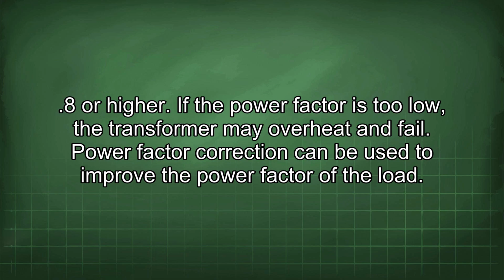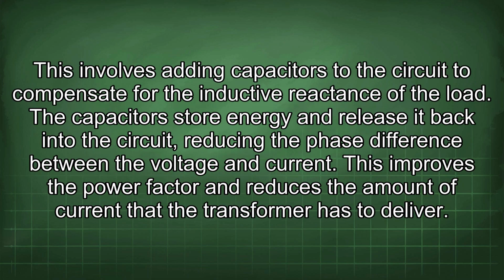Power factor correction can be used to improve the power factor of the load. This involves adding capacitors to the circuit to compensate for the inductive reactance of the load. The capacitors store energy and release it back into the circuit, reducing the phase difference between the voltage and current. This improves the power factor and reduces the amount of current that the transformer has to deliver.